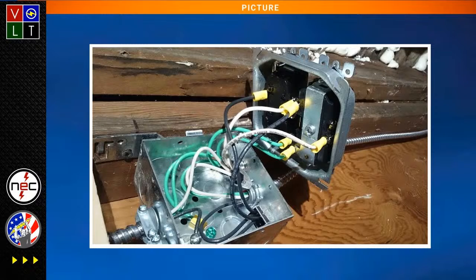And then I doubt that the receptacles themselves or the devices in that are rated for use with those crimp splices. It's been a common practice for people to use those on stranded wire, which is probably fine as long as the device is listed, which is a 110.3(B) violation if you don't have the right devices. I believe there's one brand of Hubbell that I know for sure is listed for use with those fork terminals.